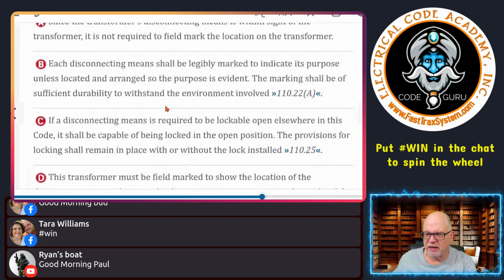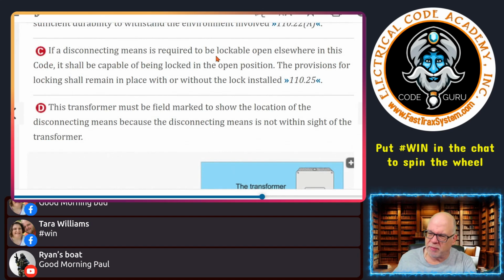All right, let's see what else we got here. So C: if the disconnecting means is required to be lockable open elsewhere in this code, it shall be capable of being locked in the open position. The provisions for locking shall remain in place with or without the lock installed. So it has to be inherent to it, or something installed, so that even if the lock is not there, it's still in place. In a panel, we use the kind that snaps into the cover or onto the breaker so it's in place whether or not the lock is put there. Those are some of the rules in 110.25 for that.